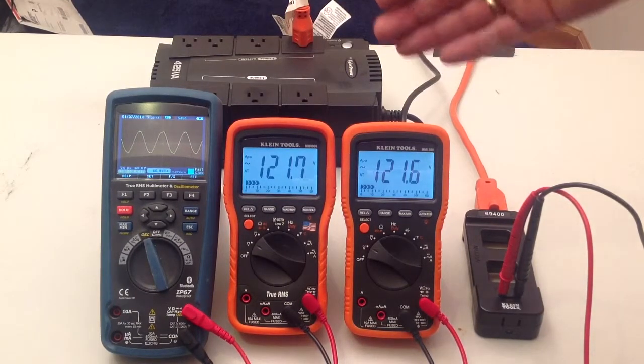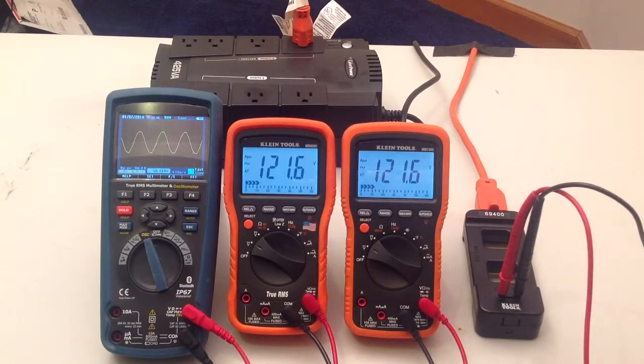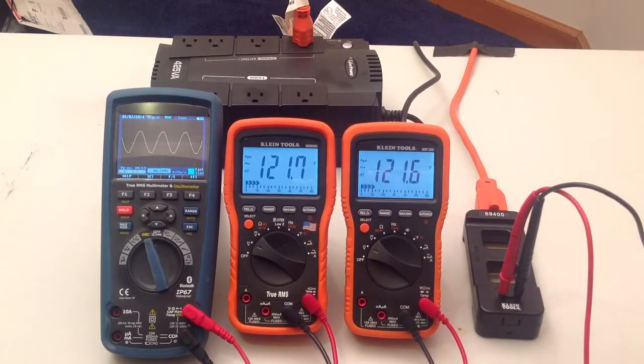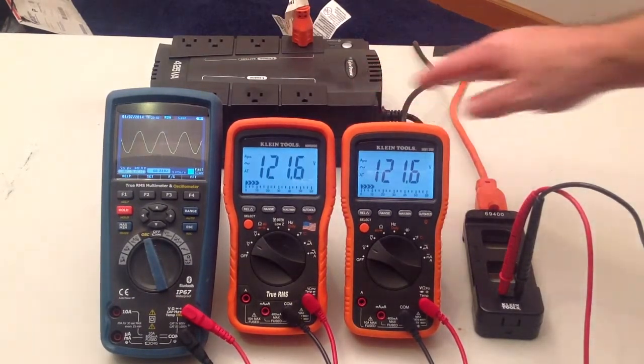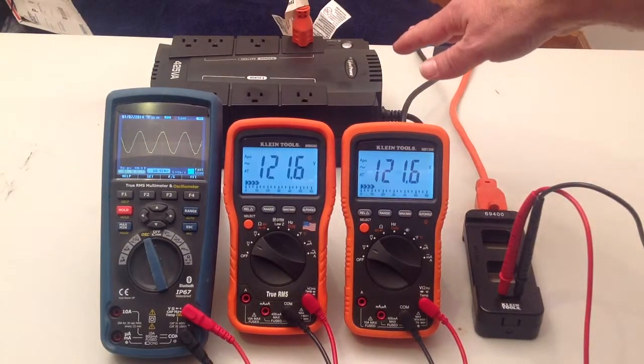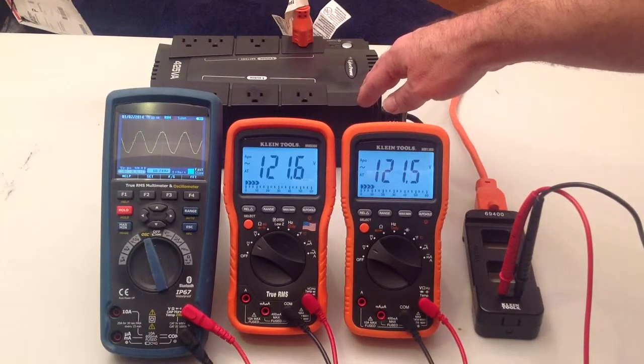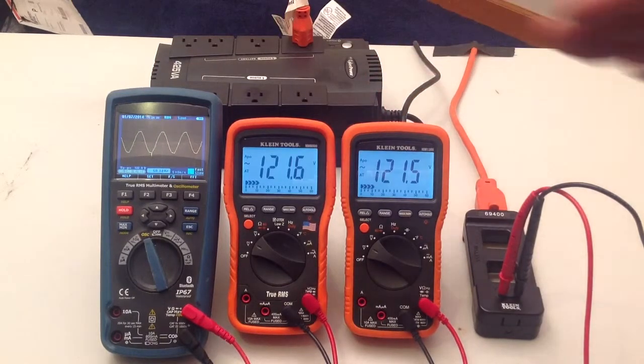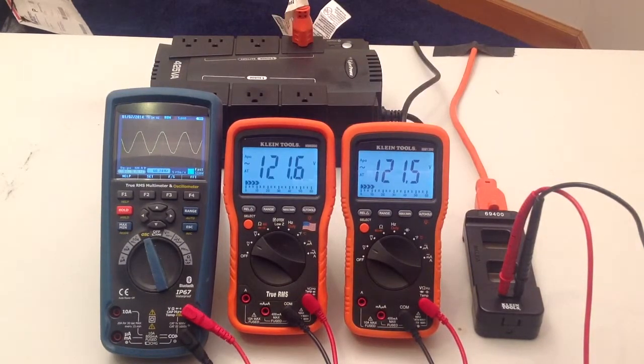Right now, because it is a pure sine wave, these two meters show the same voltage. I am using a battery backup system. I am going to kill the power to this battery backup. This guy is going to then generate an AC waveform. However, it is not going to be a clean, perfect sine wave like you see there.